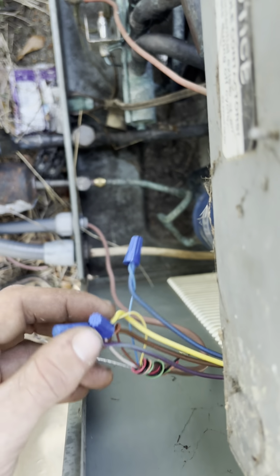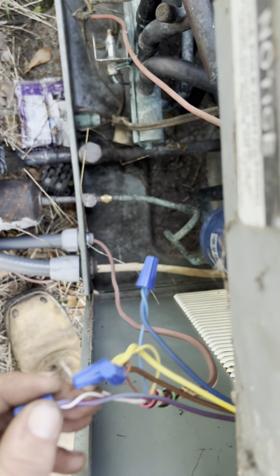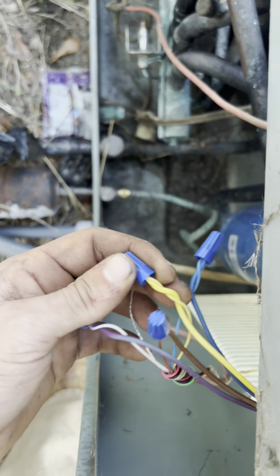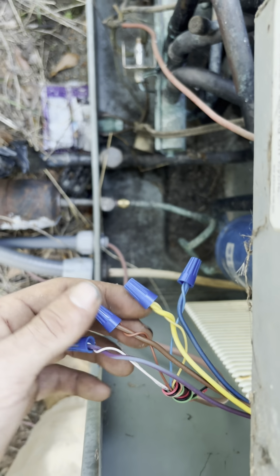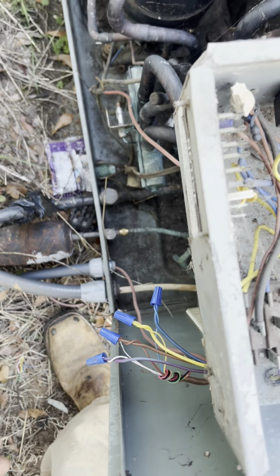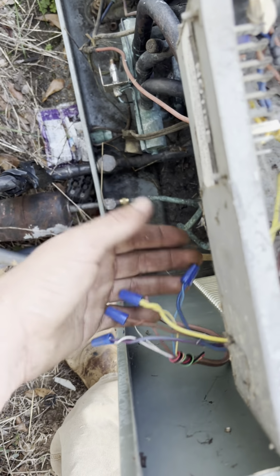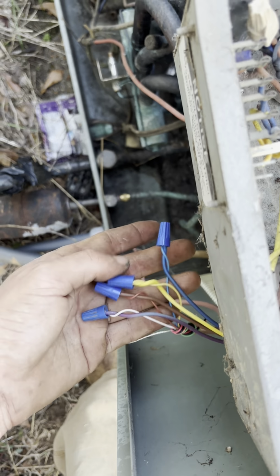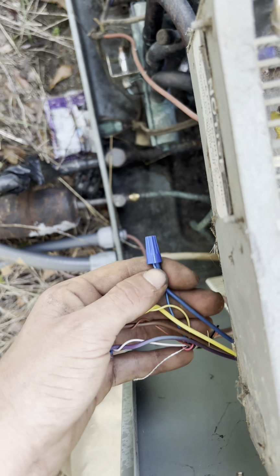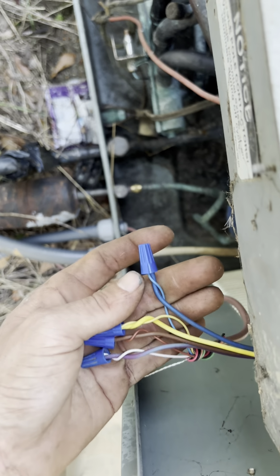Blue is reversing valve, white is defrost and heat, yellow is cool, and brown is common. It depends on what kind of unit y'all have. Some of y'all will have blue as reversing valve, some of y'all will have orange. All it means is that blue energizes in heat. All right, guys, new transformer is hooked up.